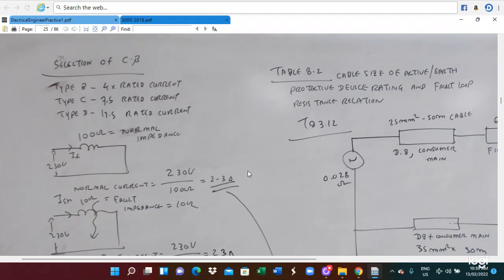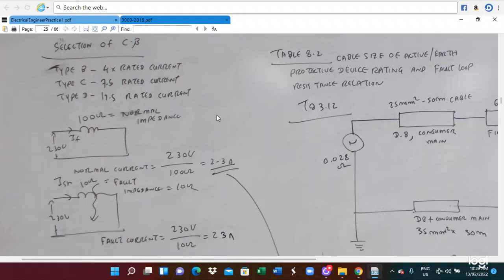Another thing is, as an electrical engineer, you also need to set the circuit breaker. When we are installing an electrical installation system, you have to protect your circuit. In this case, you need to utilize an appropriate circuit breaker. So this is the selection of the circuit breaker. There are three kinds of circuit breaker. Type B is 4 times rated current. Type C circuit breaker is 7.5 times rated current, and type D is 17.5 times rated current.